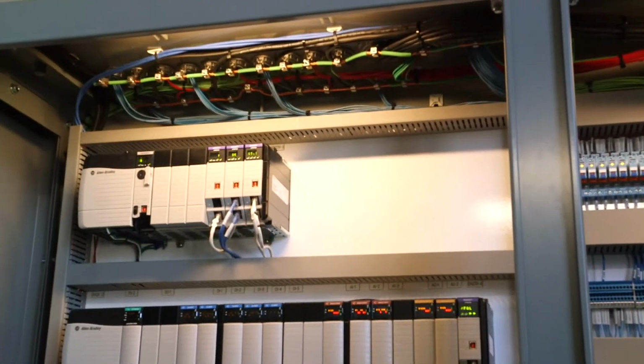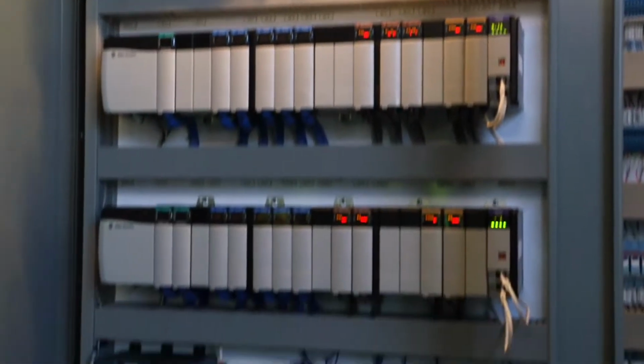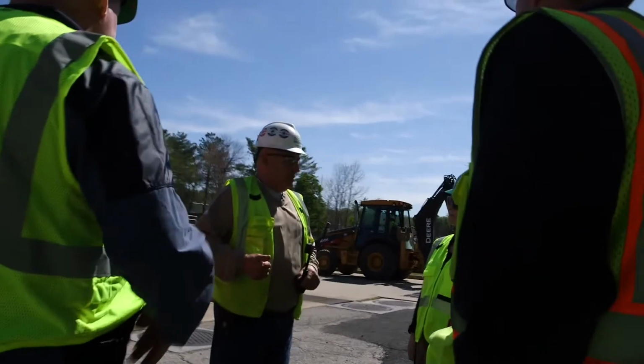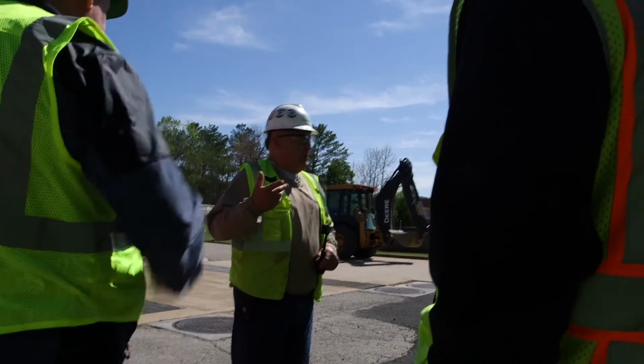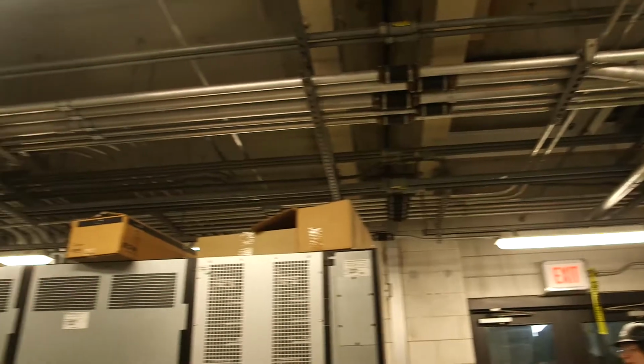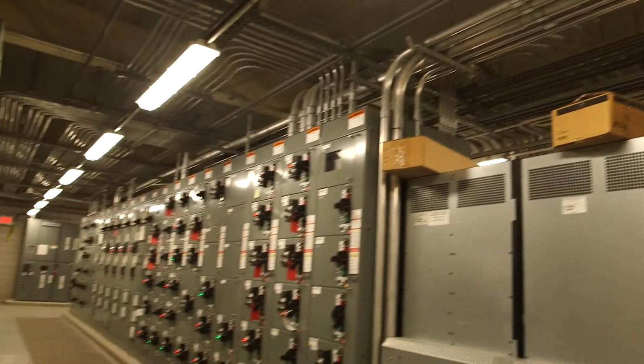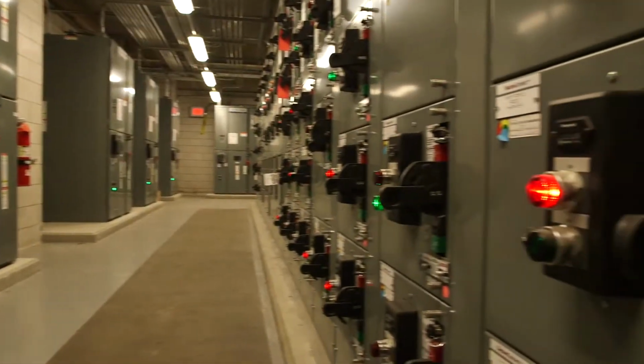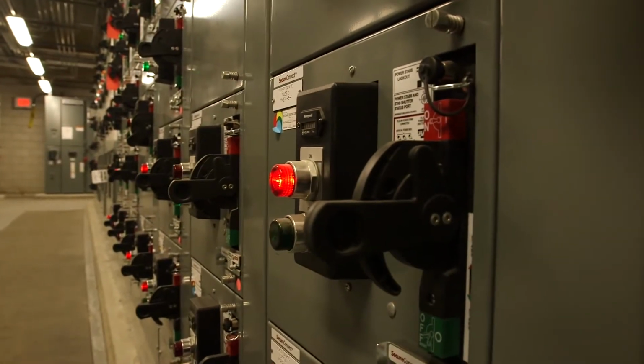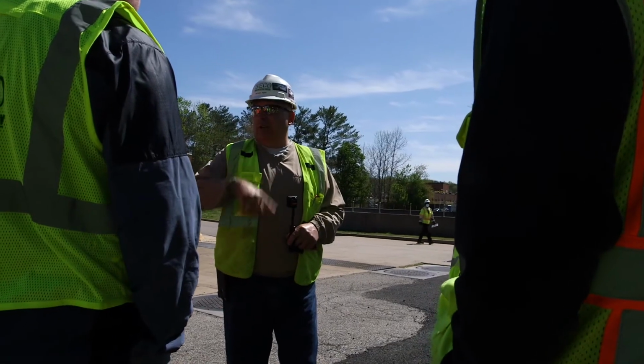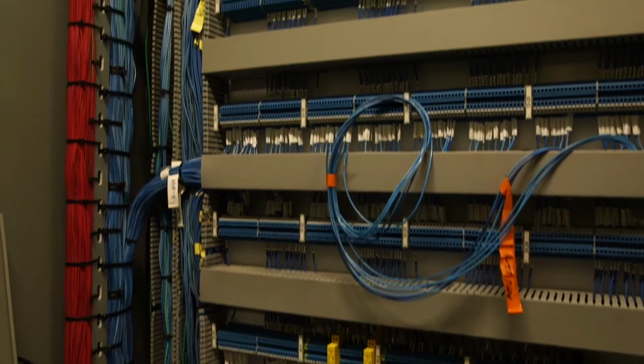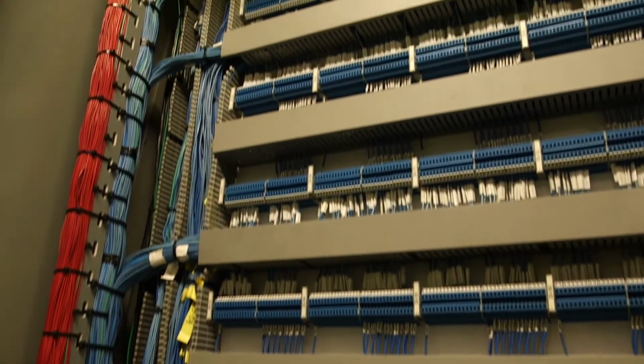It was twofold here. It was to automate the process to a higher level, and it was to provide safety — all the new motor control centers have a built-in arc flash detection system. Super high-speed contacts will drop the mains out if any flash is detected on the fiber. They actually run a fiber network inside all the equipment, and the super high-speed contact will dump the equipment if there's any flash whatsoever.